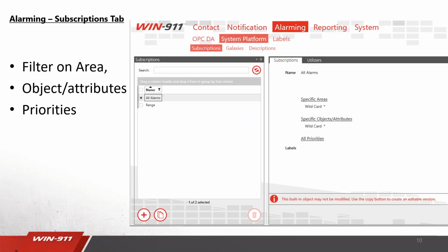We can do an area wildcard for all. This is our default, all alarms. We can do specific object names or attributes, and then we can also do it by priorities. To get to that section, again, you would open up the WIN-911 workspace from the start menu, and navigate to the alarming, down to System Platform, and to the subscriptions. Now, when you create a subscription, this is just making subscriptions available. They're not technically in use until you add them to a route. I'll show you that in a second.